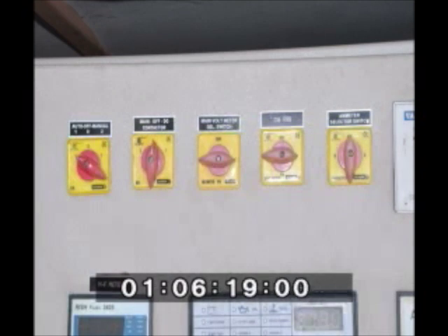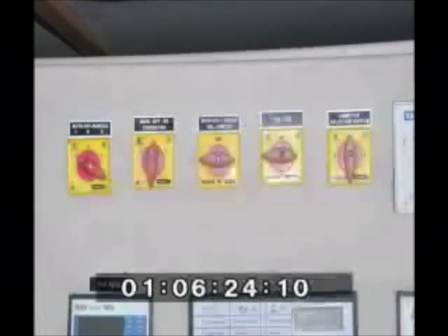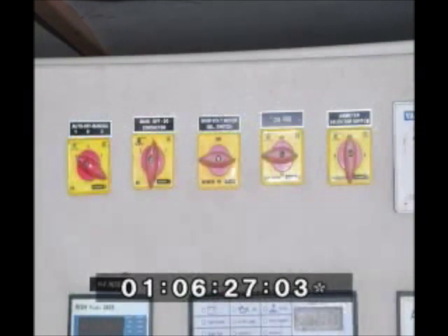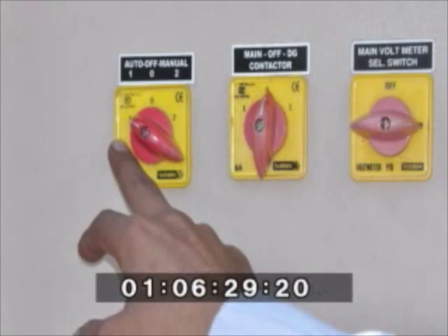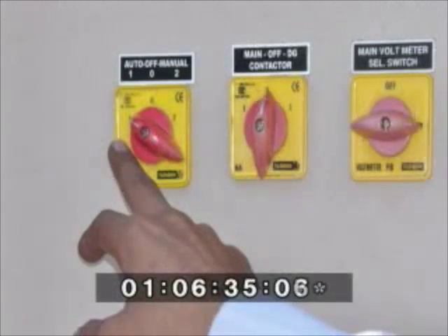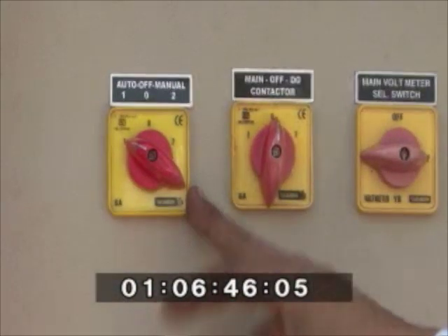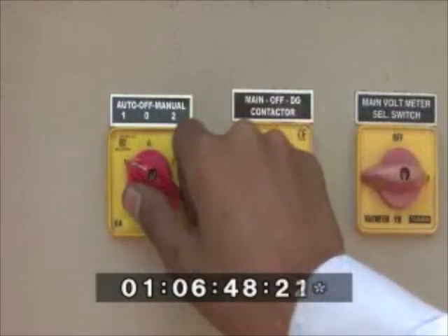We will now check the DG working in manual mode. To make the DG work manually, we need to adjust the switch on the extreme left of the AMF door. The switch has 3 positions. The left position is the auto mode, the center position is the off mode, and the right position is the manual mode. First, we will rotate the switch to the manual mode.